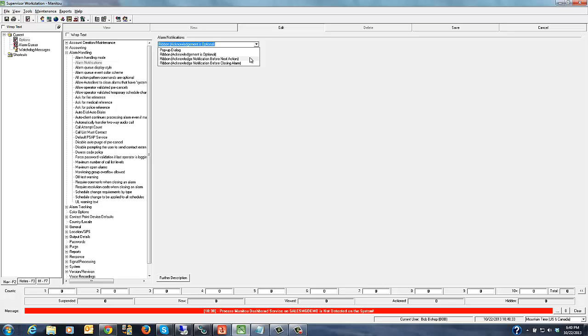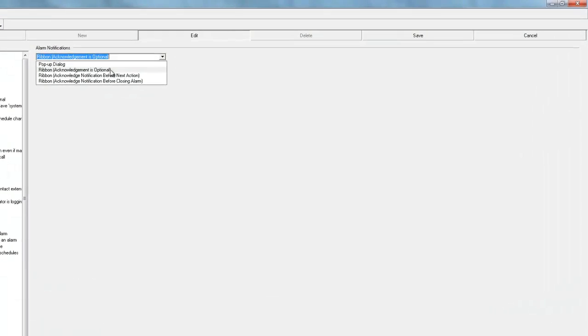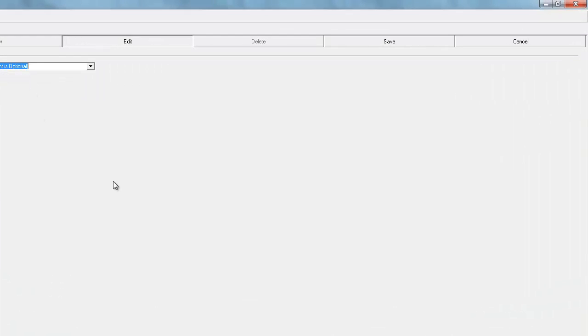The last item is to acknowledge the notifications before closing out the alarm. So that would allow the operator to go through every one of the action pattern items, but before they can actually finish and close the alarm they would need to go over there and acknowledge any of the flashing icons in the ribbon bar so that they can see all of that information before closing out and finalizing that alarm. We'll go ahead and keep this here on my demo system listed as acknowledgement is optional and we'll show you what it looks like on the front side.